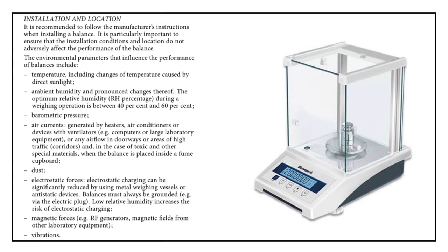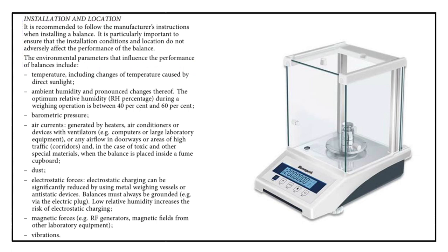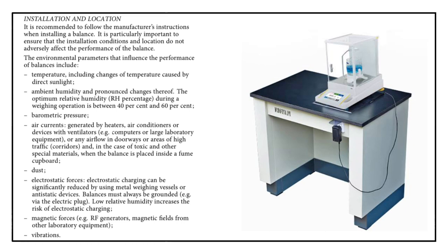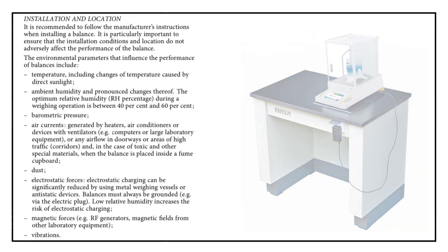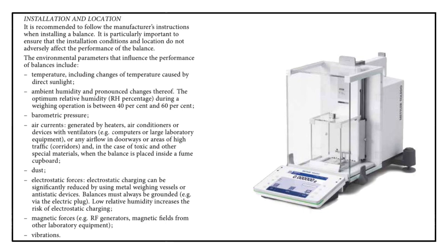Regarding installation and location, it is always recommended to follow the manufacturer's instructions when installing a new balance. The surrounding conditions and location must not affect balance performance. Environmental conditions that generally affect balance performance include temperature, humidity, barometric pressure, air currents, dust, electrostatic force, magnetic force, and vibrations.